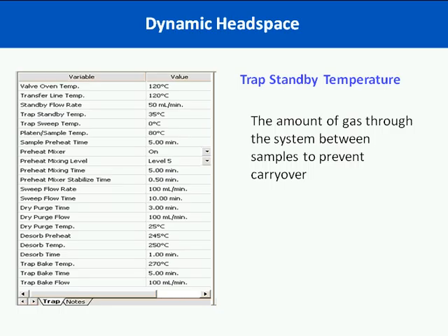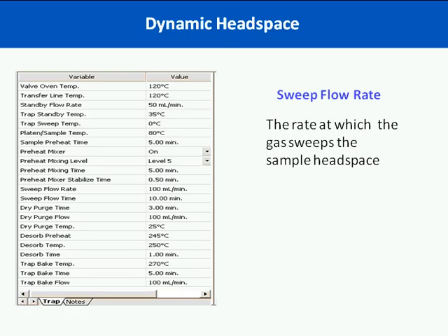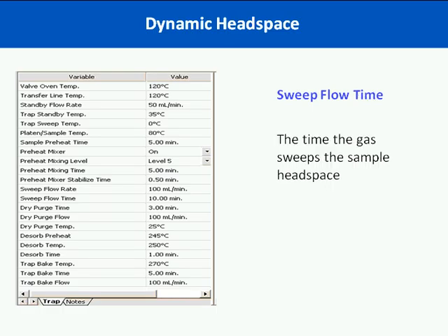The trap standby temperature is the temperature that the trap must reach before the next sample can begin — this assures that each sample is run under the same temperature and conditions. A good setting for the trap during standby is about 35 to 45 degrees C. The sweep volume is dependent on two variables: sweep flow rate and sweep flow time. The sensitivity of your analysis can then be controlled by the sweep volume. So if you're trying to increase the sensitivity, adjust both the sweep flow rate and the sweep flow time.